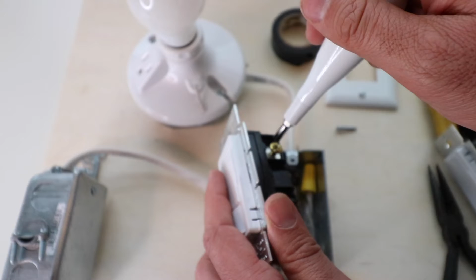Now, for the occupancy sensor, depending on how it comes in the package, you might need to loosen these up a little bit. Ideally, when doing lighting, you get better contact if you hook it on the side typically than through the back. It just depends on the manufacturer, but the surface area typically has more contact when you hook it around than the back mount, even though both of these light switches have a back mount option, as you can see here. So when possible, it's usually best to hook it around.